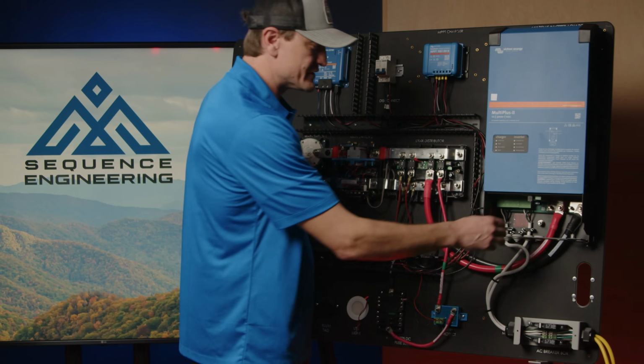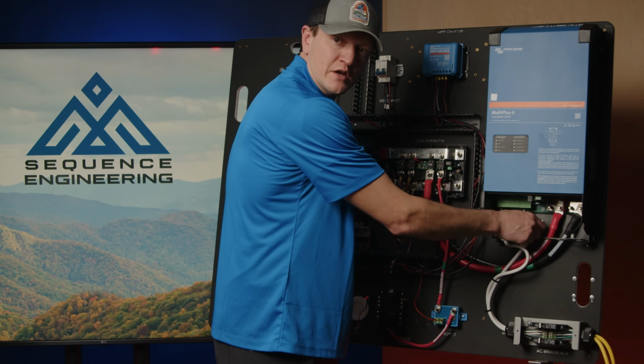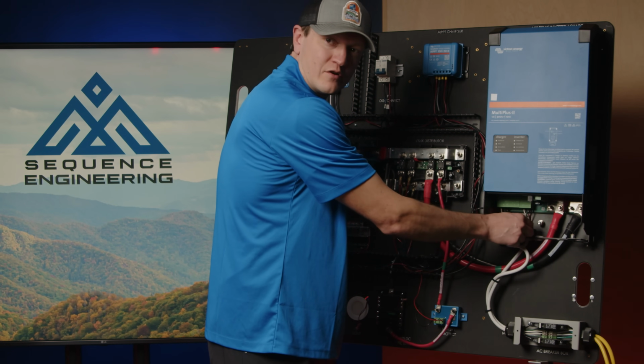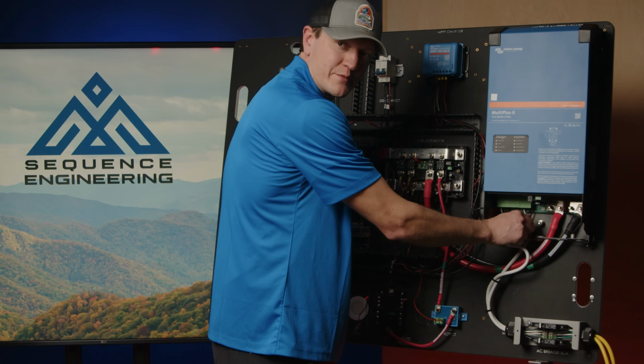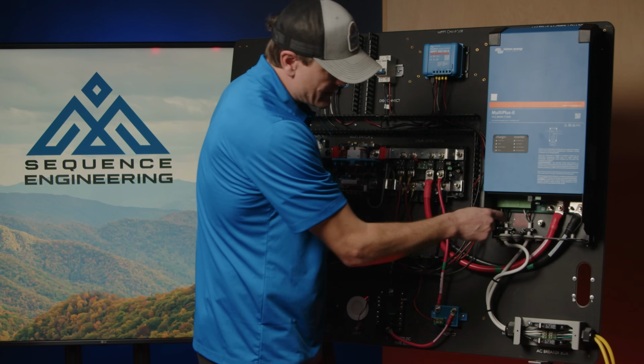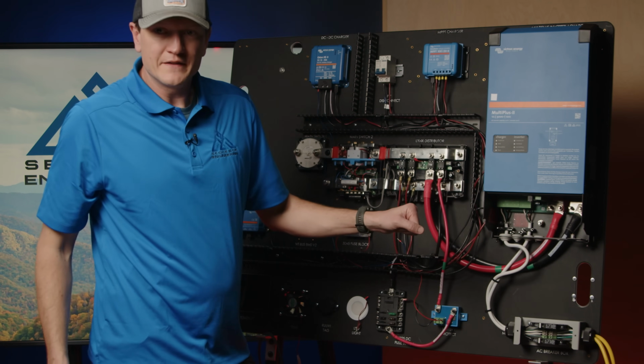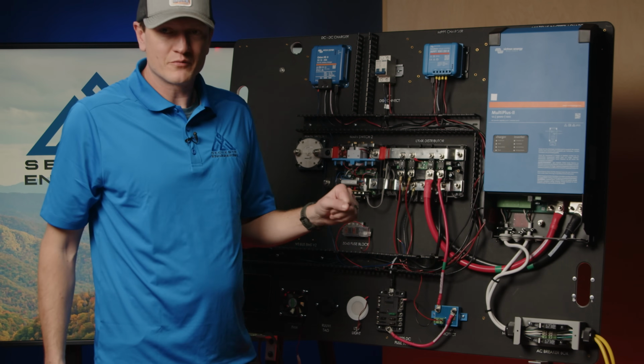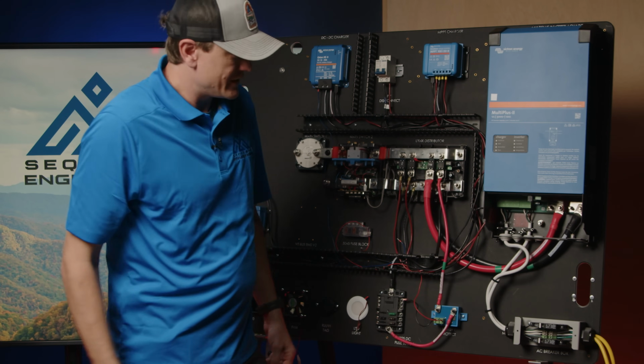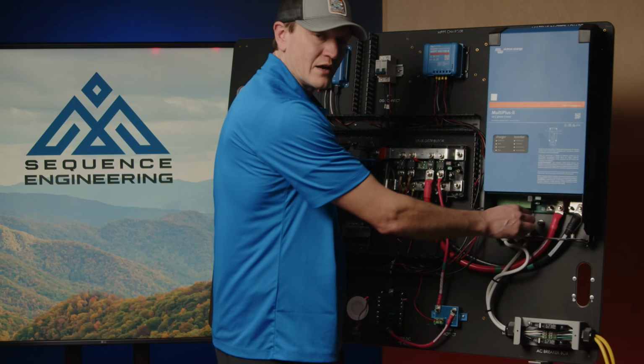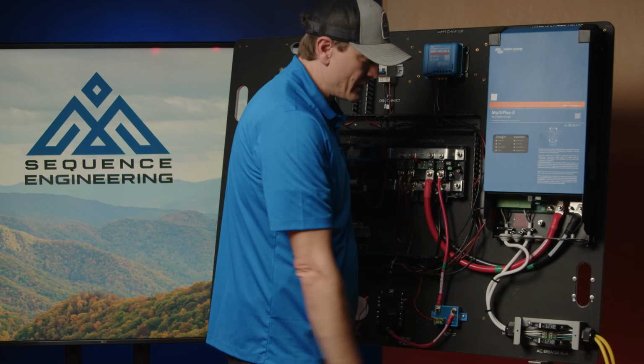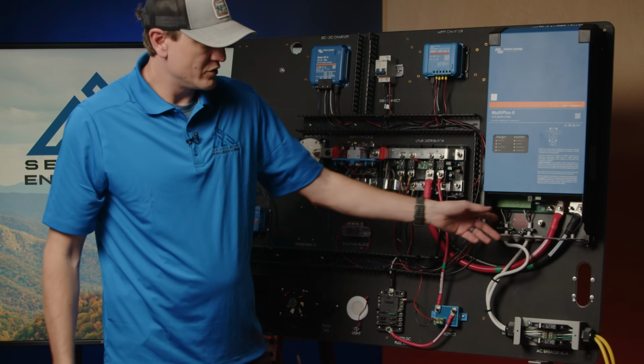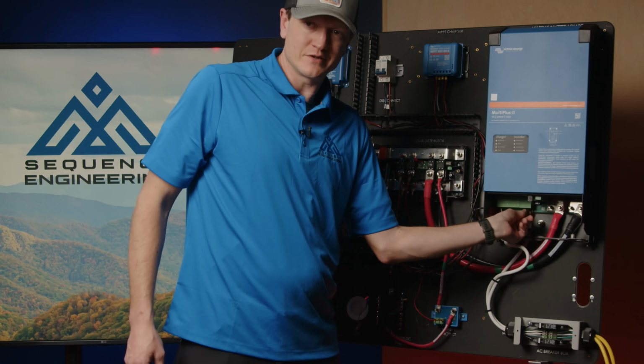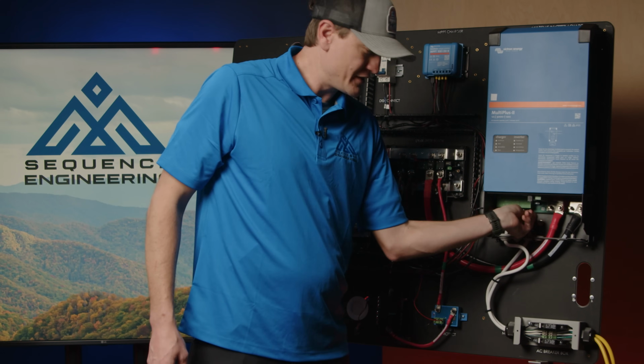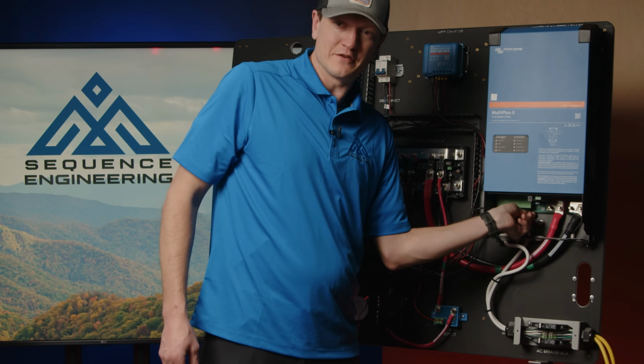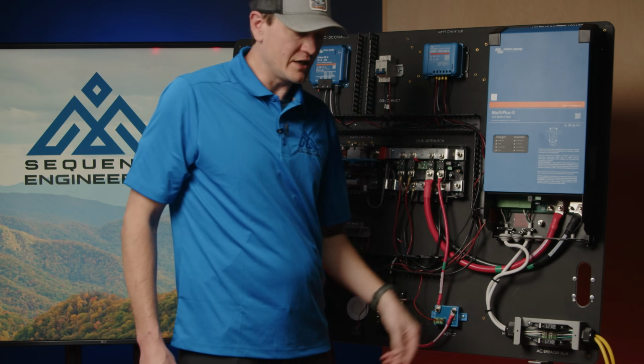The other thing to note is that you want to snug up the wire clamps they've provided. Grab your socket and snug those down so they grab the wire. In the event you didn't get a great insertion on that spring clamp, at least the wire won't go anywhere. You really want to give these a tug, not a snug, to make sure they're not going to come out of those spring terminals. Make sure you've got good engagement.